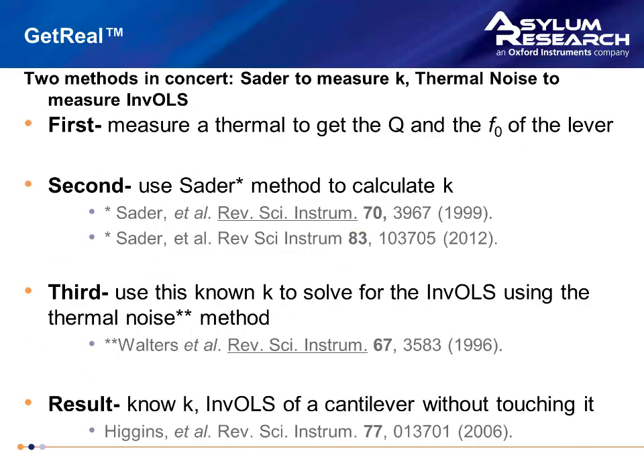So, GetReal is going to use two methods to calibrate the spring constant and the sensitivity of the cantilever without having to perform that first force curve. Basically, this is an extension of a technique originally developed by researchers at Asylum, Trinity College, and the University of Melbourne, and it's referenced at the bottom of this slide. First, it's going to take a thermal of our cantilever to measure the Q and the resonance frequency. Once we have those two values, we can then use the Sader method to calculate the spring constant of the cantilever.